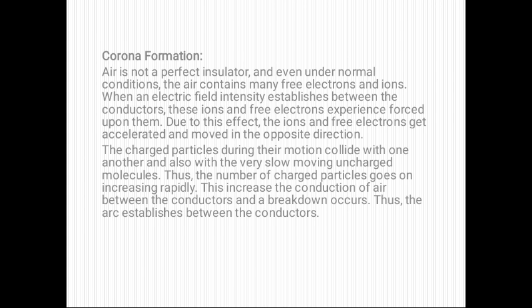The charged particles during their movement collide with one another and also with the very slow moving uncharged molecules. During this process, the number of charged particles goes on increasing rapidly. So, this increases the conduction of air between the conductors and a breakdown occurs. Thus, an arc is established between the conductors, with a hissing noise. This is the formation of corona.